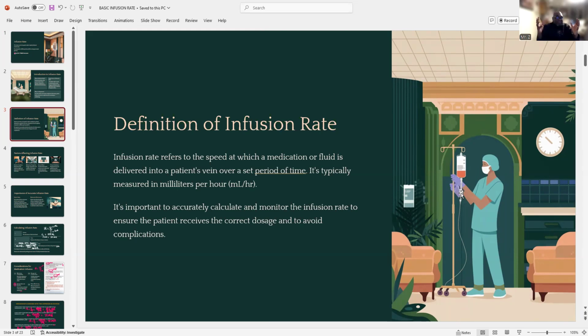If you have 45 drops per minute, you have to release the clamp a little bit, very slowly, so you can read your time and count right there, 45 drops per minute. So you need your drop count to be a whole number. You need those little drops to go into that chamber, and you have to manually count to 45.